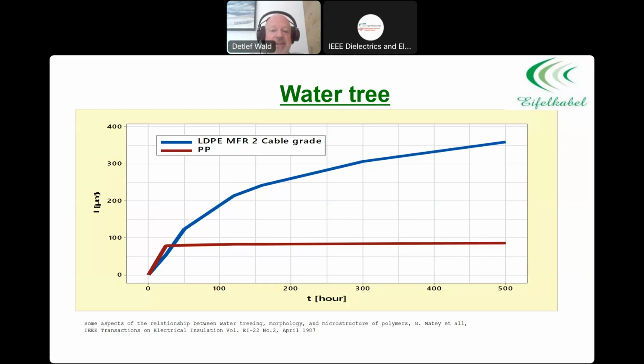Speaking of another thing about contamination, there are comparisons done on water treeing, which is known, as contaminations can create water trees under certain tests. So here's a comparison done of polypropylene with an LDPE cable grade. As you can see, it's not that new. It has been published in 1987, so that was before I started working in the cable industry. And polypropylene there is better than polyethylene in this specific test.